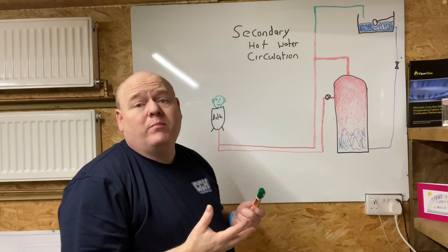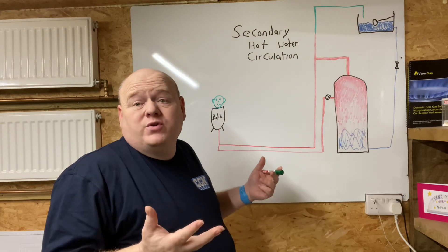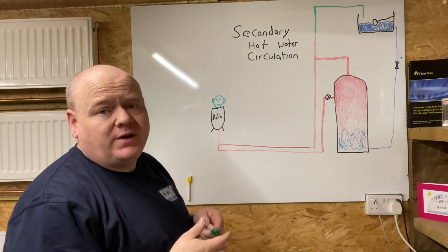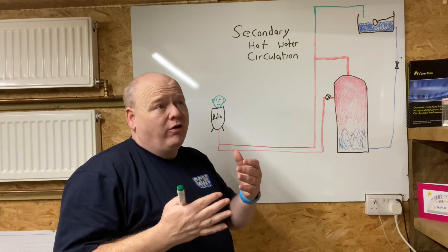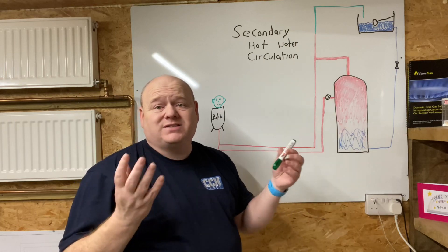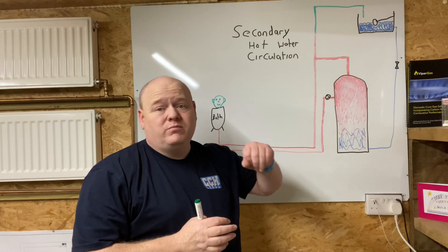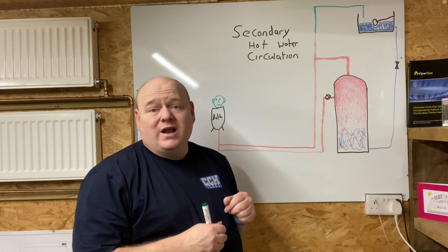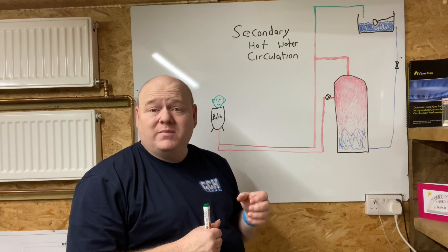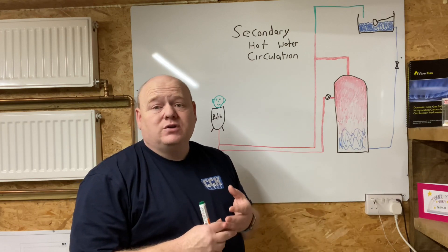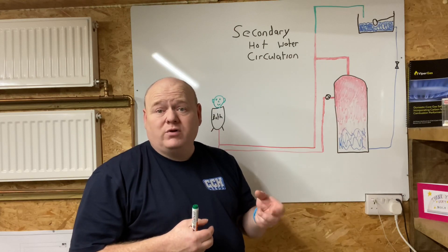What is a pumped hot water system or pumped return, and why would you need it? If you imagine a large house, commercial property, hotel, or hospital — large premises — the boiler room could be half a mile away, and if you turn the hot tap on it would take a very long time to get hot water to the tap. You need to make it so that when you turn the tap on, the hot water comes out as soon as possible.